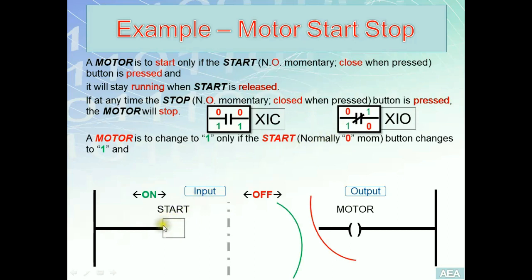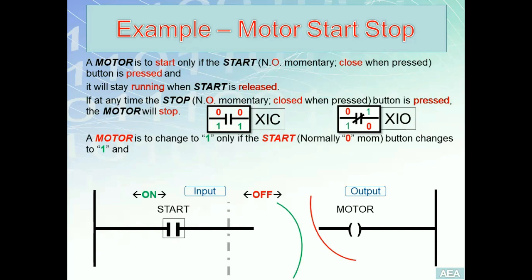For the start button, XIC or XIO? The requirement says the motor is to change to one when the input changes to one. The key concept is that for deciding which instruction to use, we consider the changed state of the input, not the default state. The default state of the normally open start switch is zero; when pressed it closes and changes to one. Since the motor changes to one when start changes to one, we use XIC for start.